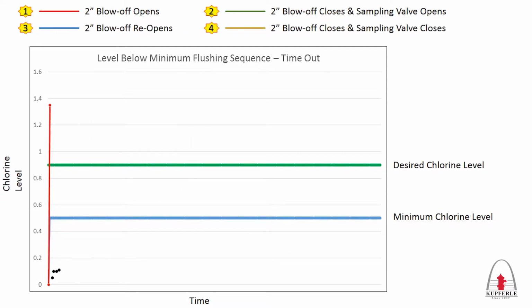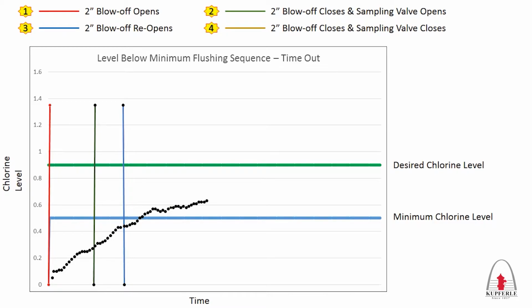If the unit is set to continuously sample and the sampled water's residual level is detected to be below the program minimum chlorine level, the unit will begin to flush and continue to sample. If the sample does not achieve the program desired residual level, the unit will continue flushing until the program maximum total flushing time has been reached. Both valves will close, ending the sampling sequence. Initial and final chlorine residual levels, time of day, and flush duration data is recorded onto the PLC.